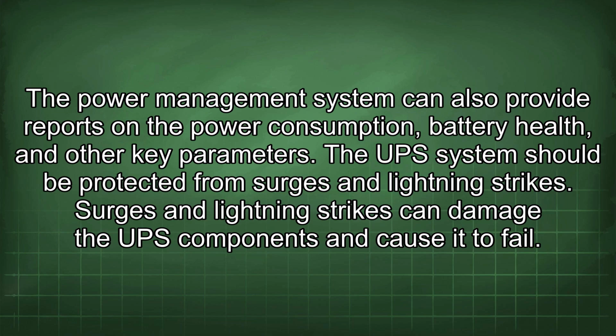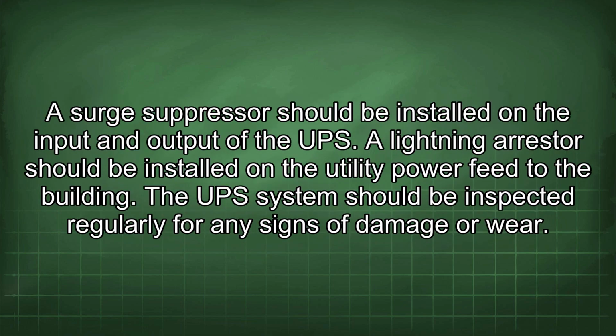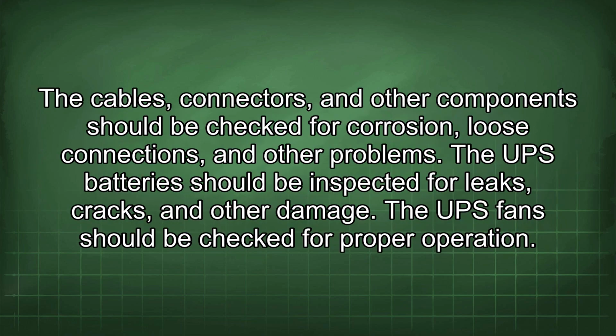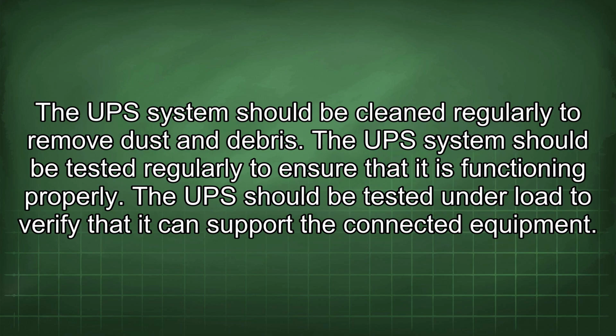The UPS system should be protected from surges and lightning strikes. Surges and lightning strikes can damage the UPS components and cause it to fail. A surge suppressor should be installed on the input and output of the UPS. A lightning arrestor should be installed on the utility power feed to the building. The UPS system should be inspected regularly for any signs of damage or wear. The cables, connectors, and other components should be checked for corrosion, loose connections, and other problems. The UPS batteries should be inspected for leaks, cracks, and other damage. The UPS fan should be checked for proper operation. The UPS system should be cleaned regularly to remove dust and debris.